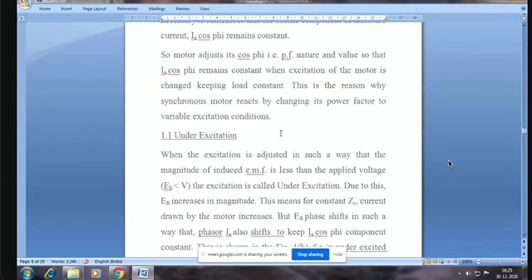Okay. So then if you go on increasing IF beyond this point where the power factor had become unity, we understand that it becomes over excitation. Any current higher than the field current which makes the power factor 1, that means any current higher than that critical field current which makes the power factor 1 is called over excitation. So towards right of this, we see over excitation. And we have discussed earlier that when the excitation is over, excess, the power factor becomes leading.